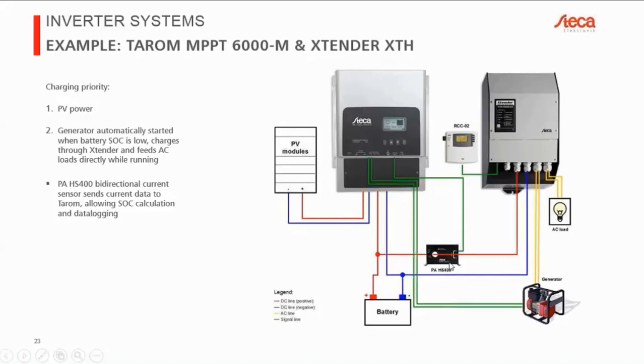So this current sensor can sense that energy going either out or into the battery and reports that energy back to the charge controller. Now, the charge controller can use that, first of all, to show you how much energy is flowing in and out of your battery, to log that data either locally in internal memory or on an SD card, or it can also use that to calculate the state of charge of your battery. And again, to calculate the state of charge, we need to know the current going in and out of the battery. So we need to have an external current sensor if you're connecting an inverter to the battery. And then finally, I don't have that in this session, but this charge controller could also be connected to an internet portal. So then you would also need the current sensor to be able to see how much energy is flowing out to the inverter.